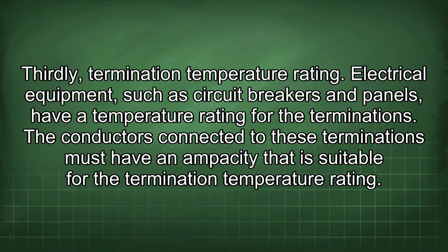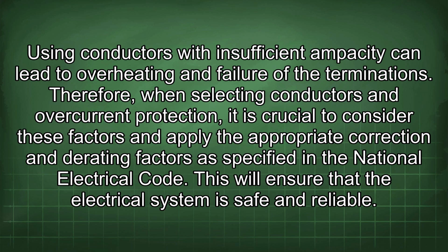The conductors connected to these terminations must have an ampacity that is suitable for the termination temperature rating. Using conductors with insufficient ampacity can lead to overheating and failure of the terminations. Therefore, when selecting conductors and overcurrent protection, it is crucial to consider these factors and apply the appropriate correction and derating factors as specified in the National Electrical Code. This will ensure that the electrical system is safe and reliable.